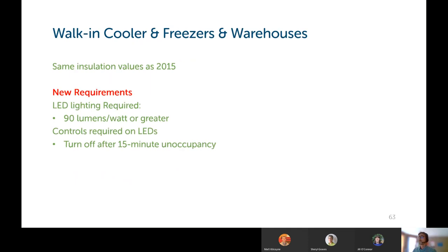Walk-in coolers, freezers, and refrigerated warehouses: all of the insulation values of those cooled boxes and buildings are the same as 2015. The new requirements are on the lighting side. It says LED lighting is required in these spaces that are 90 lumens per watt or greater. Controls are required on those LEDs that turn the lights off after 15 minutes of unoccupancy.